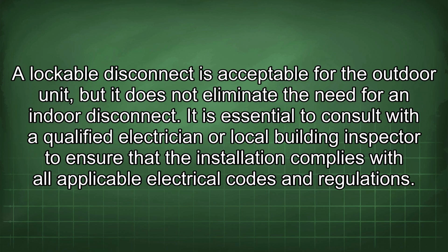A lockable disconnect is acceptable for the outdoor unit, but it does not eliminate the need for an indoor disconnect. It is essential to consult with a qualified electrician or local building inspector to ensure that the installation complies with all applicable electrical codes and regulations.